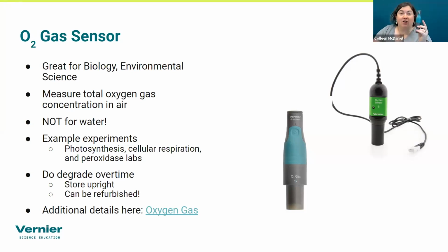These sensors, like the pH sensor, do have a lifespan to them. But they can be refurbished, since the electrochemical cell inside of them can be replaced. It's about $100 to do the repair or replacement for those, and typically what I tend to see is these can last, like the pH probe, anywhere from 6 to 8 years.